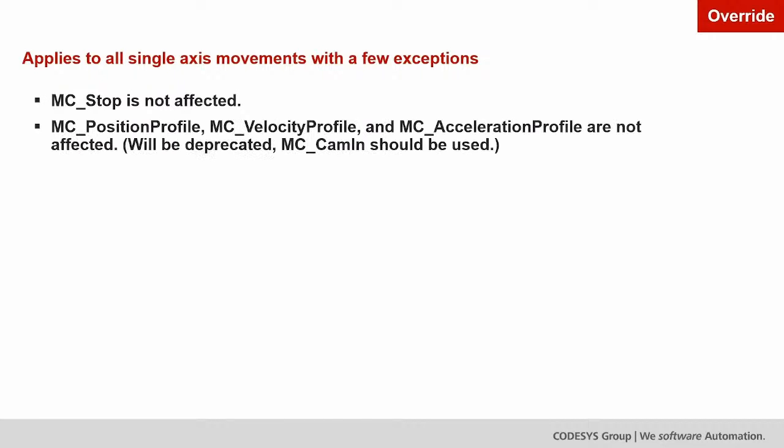The override applies to all single axis movements with a few exceptions. MC_Stop is not affected at all. Similarly, MC_PositionProfile, VelocityProfile, and AccelerationProfile are not affected. By the way, these function blocks will be deprecated in the future. We recommend to use MC_CamIn instead.